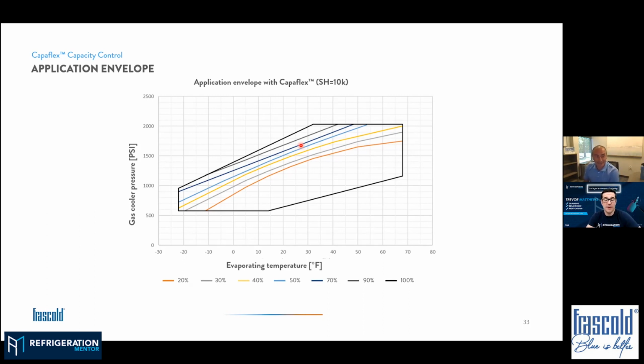Yeah, and it's great because it's something more people need an idea of, because you might have a big operation envelope for your compressor, but depending on where you're running that compressor, the design conditions, you might be running outside the envelope even though the envelope is that big. I've had lots of conversations with technicians and they're like, well, isn't this the operation envelope? Yes it is. But in these design conditions, it's not. So I like that.